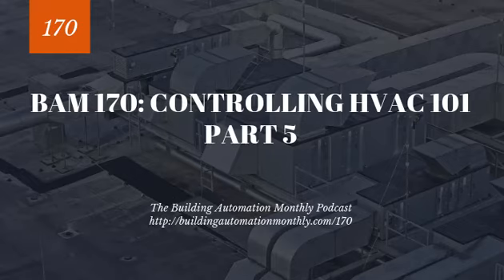Or 45 going in and 47 coming out. There's a variety of different ways that this would show itself. It's just important to realize that that means you most likely have a flow issue, especially if the incoming temperature is accurate. So, assuming that your systems are properly balanced, mixing valves and variable speed pumps are going to enable you to maintain a pressure drop, which is another concept we'll talk about in just a second, and therefore an adequate flow rate to maintain your design DeltaT, right?